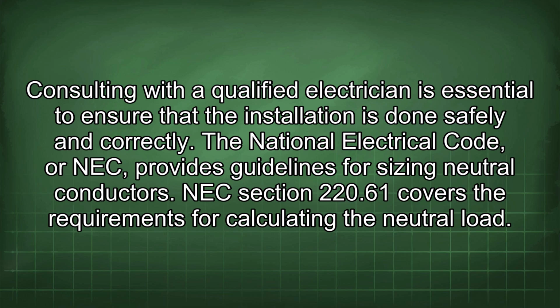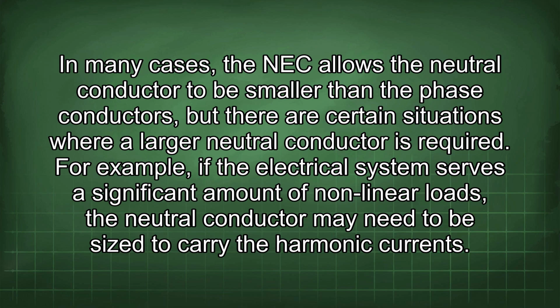The National Electrical Code, or NEC, provides guidelines for sizing neutral conductors. NEC Section 220.61 covers the requirements for calculating the neutral load. In many cases, the NEC allows the neutral conductor to be smaller than the phase conductors, but there are certain situations where a larger neutral conductor is required. For example, if the electrical system serves a significant amount of nonlinear loads, the neutral conductor may need to be sized to carry the harmonic currents.